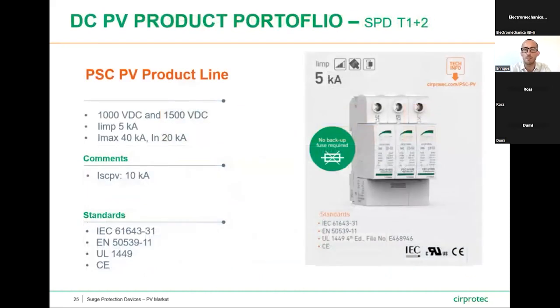The first one is our SPD type 1+2 product range. This is our PSC PV product line in Cirprotec. We have solutions for 1000 volts DC and for 1500 volts DC as well, according with the market needs worldwide. This product line is tested under the Iimp 5 kA for the type 1 test requirements, and then for the type 2, we have an Imax 40 kA and an In 20 kA. This SPD also shares the parameter Iscpv, which is the maximum current withstand capacity in case of short circuit, about 10 kA. It's manufactured under the standards IEC in an international way, EN in Europe, and is certified under the UL, and for sure is CE marked.